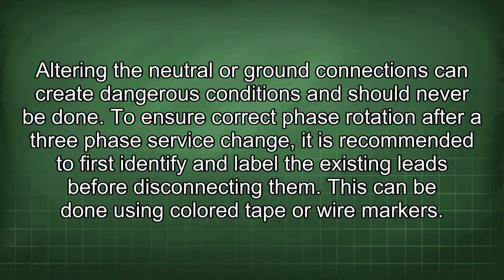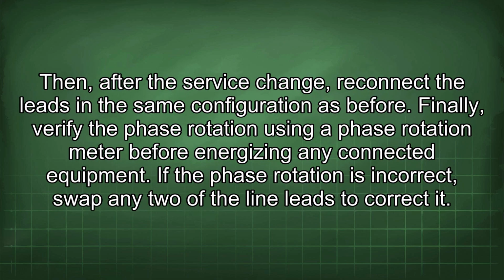To ensure correct phase rotation after a three-phase service change, it is recommended to first identify and label the existing leads before disconnecting them. This can be done using color tape or wire markers. Then, after the service change, reconnect the leads in the same configuration as before. Finally, verify the phase rotation using a phase rotation meter before energizing any connected equipment. If the phase rotation is incorrect, swap any two of the line leads to correct it.